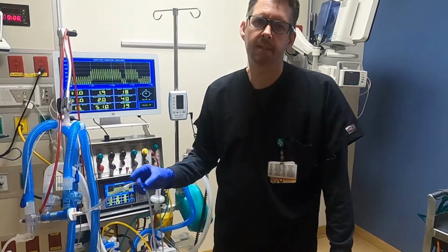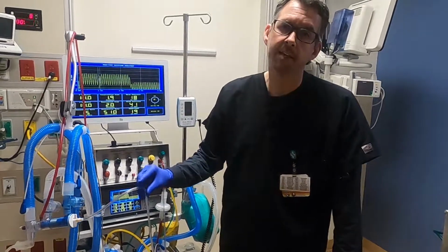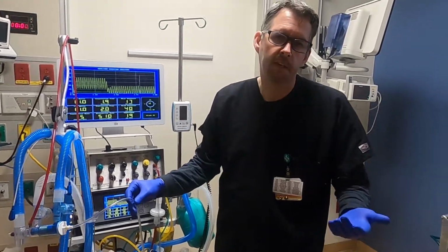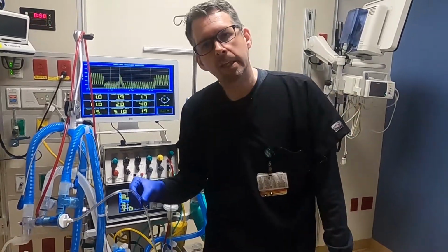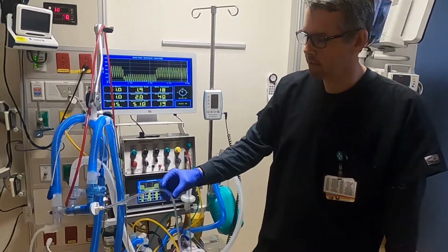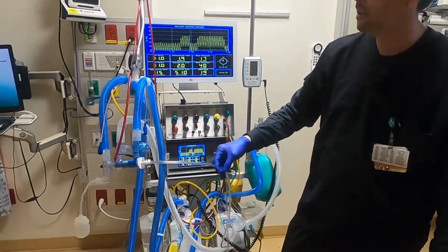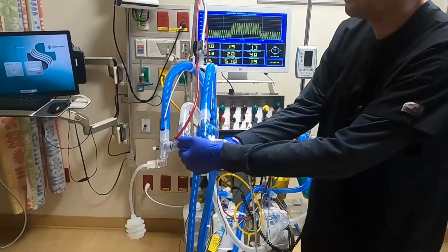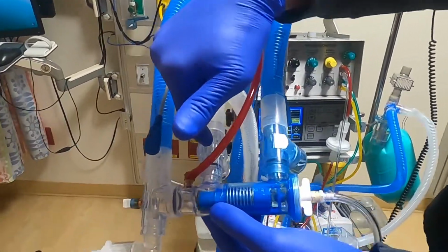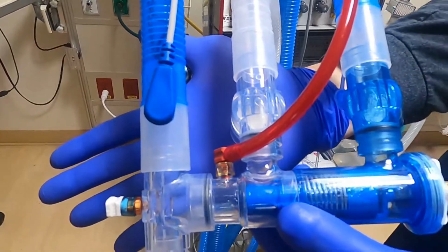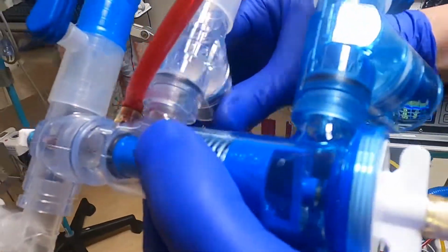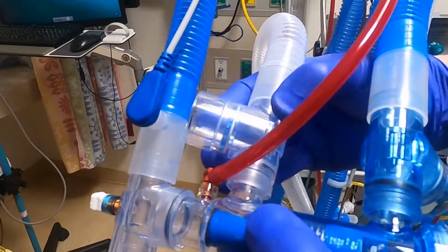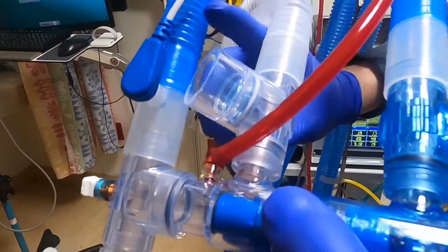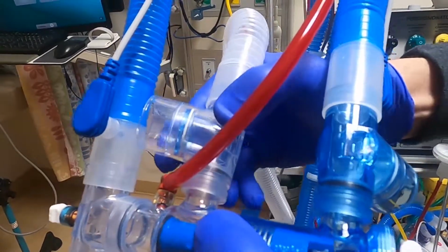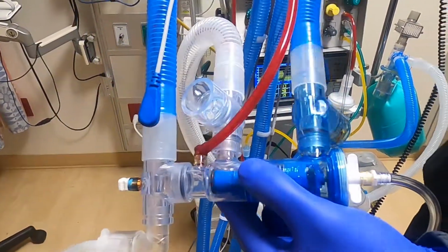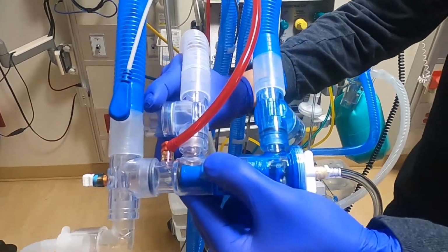The most common way that this can get occluded is by getting kinked, usually in the bed rails, or sometimes it can get pinched if somebody's leaning on it. So just be aware of that. Just keep this in a clear space at all times. The other really important thing is this is where the patient is exhaling. So if this becomes blocked, they're not going to be able to exhale very easily. So make sure that this stays in open air. And you can see it's nice because this actually moves around, so as you're repositioning the patient, you can move these so they're not blocked and the patient can exhale easily.